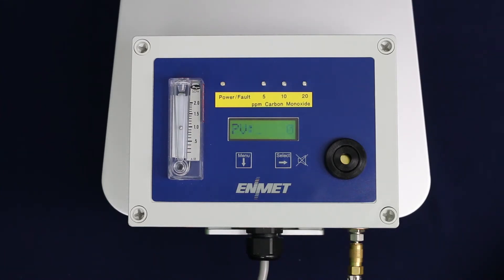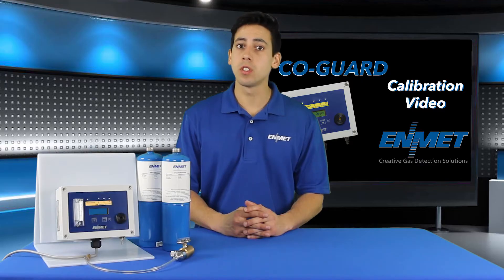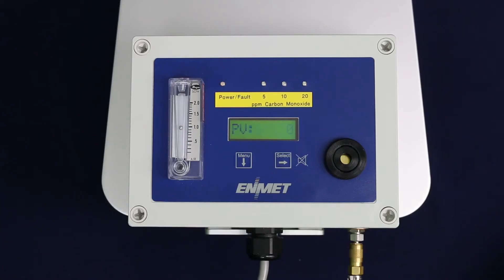The CO-GUARD will monitor the sensor signal for stability for 30 seconds. If the sensor signal is stable after 30 seconds and within tolerance, the new zero point will be accepted and CAL OK will be displayed, indicating a successful zero.